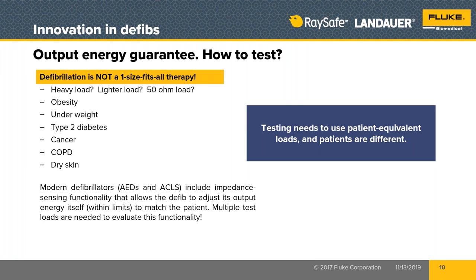So it's important because, as you can see on the slide, there are lots of different reasons why the patient's resistance to the energy setting is going to be a problem. And so the newer defibrillators have built into them a sensing circuit that's part of the charging circuit of the defibrillator, measuring the transthoracic, or across the chest, impedance of the patient, sensed through the paddles or these pads that are placed on them. Then it's able to adjust itself slightly within some limits so that what you set is what you get. And that's what I mean by output energy guarantee.